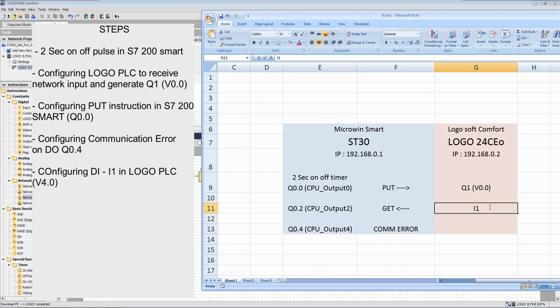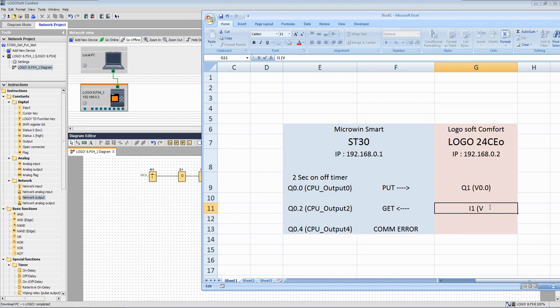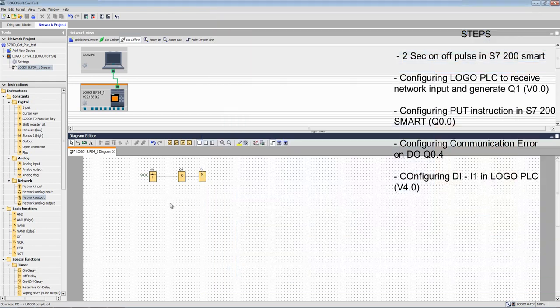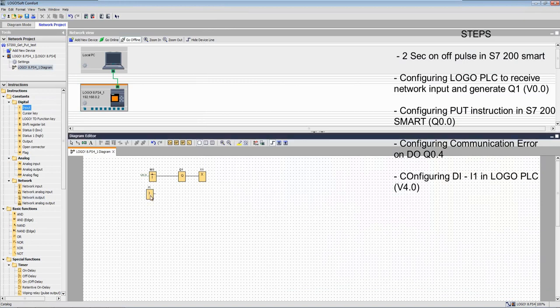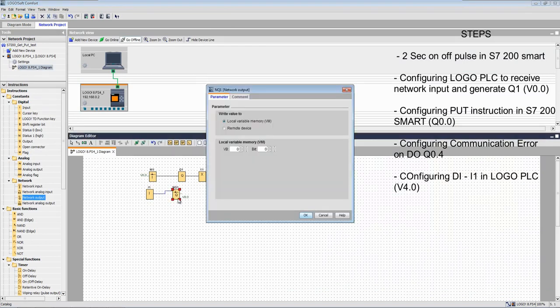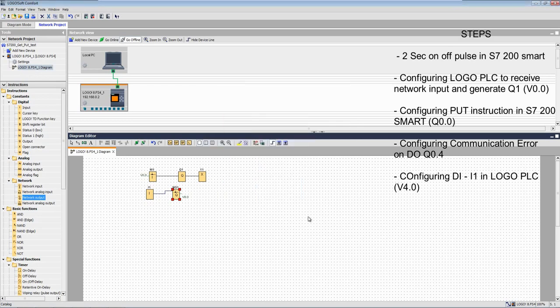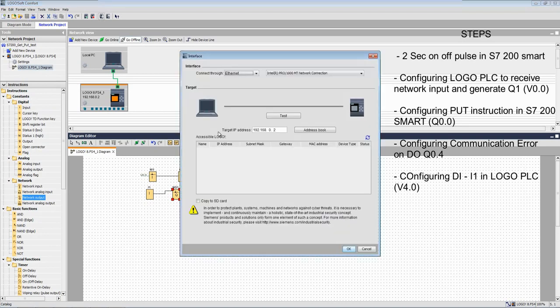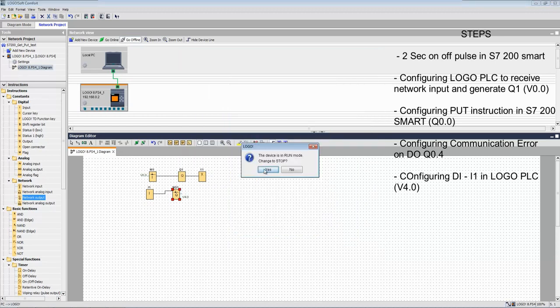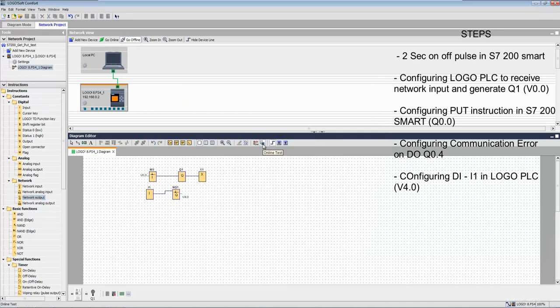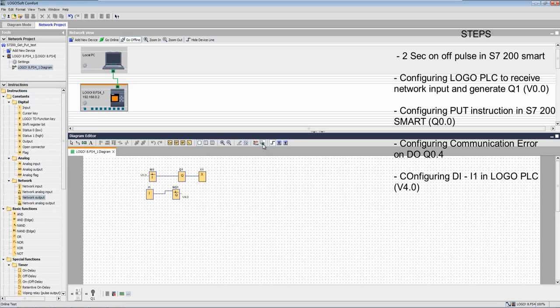Now we will configure the I1 in Logo PLC and then we will read the status of I1 in our ST30 PLC, sending status of I1 to network output. Say for example we are placing this value to V4.0. Taking online, now I am giving input 1 to the PLC and you can notice here red color.